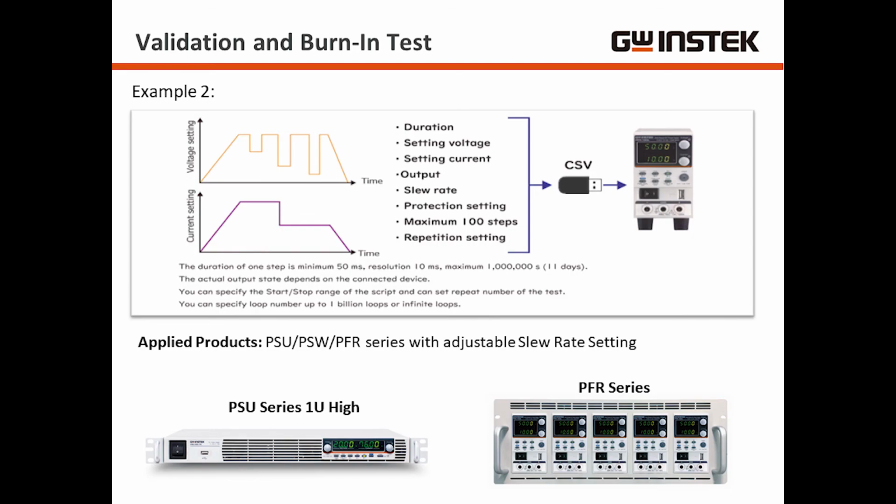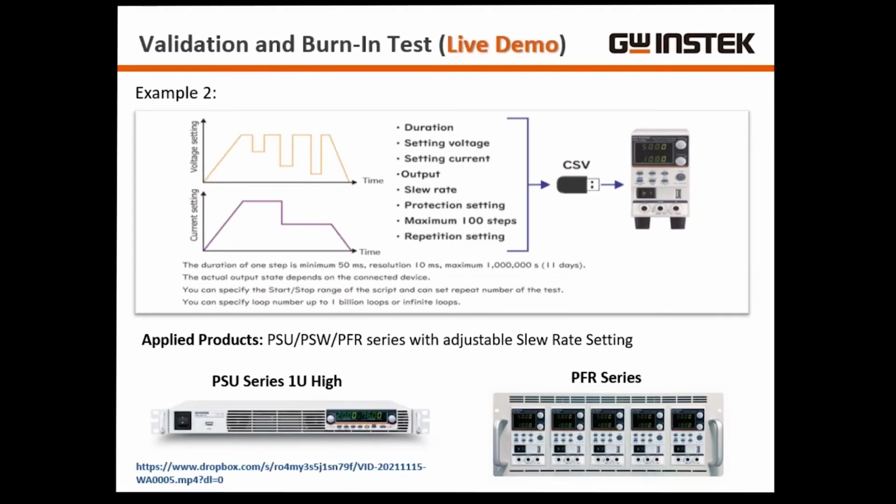Now, I will say for this type of sequence, for these types of power supplies, don't expect response time in the microseconds, probably about 100 milliseconds is what you're able to do. So it's pretty fast. If you do need something faster than that, we can talk about what we can do on our next segment, on our ASR that we'll talk about in the next couple slides.